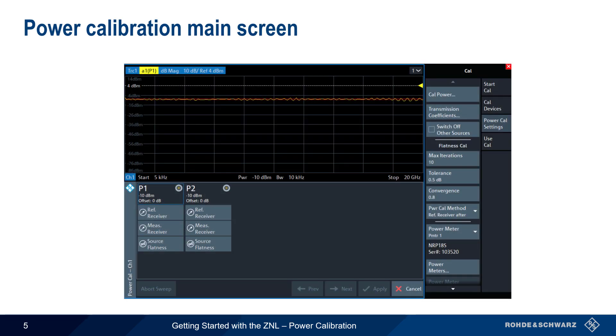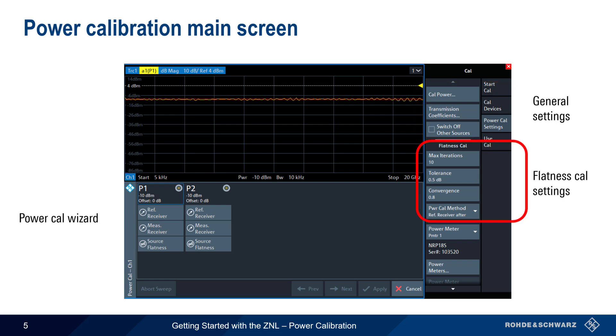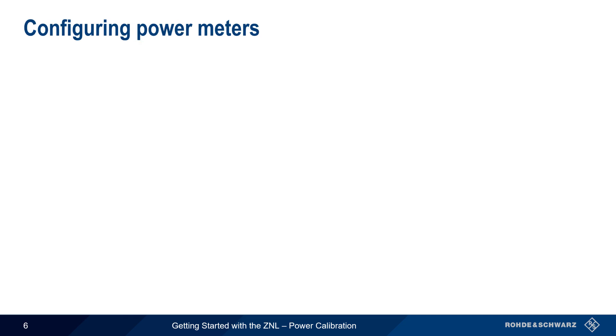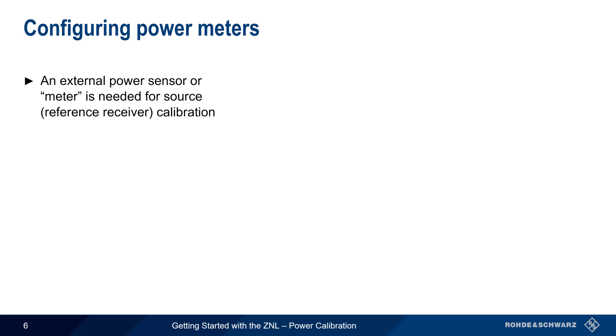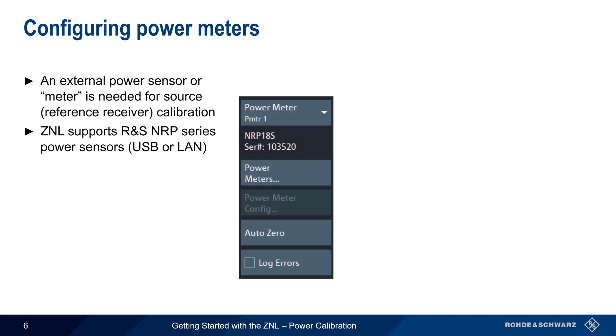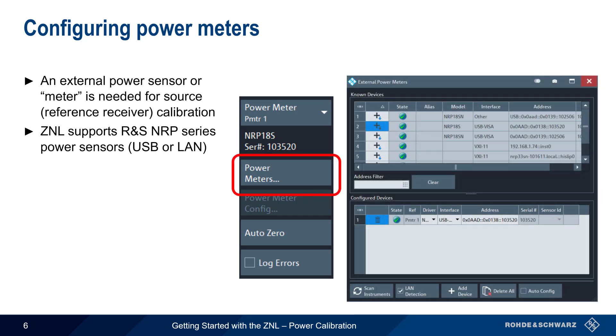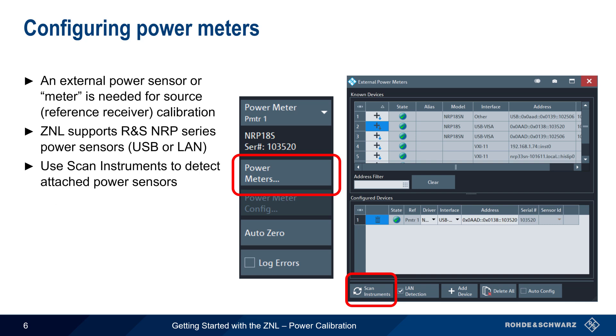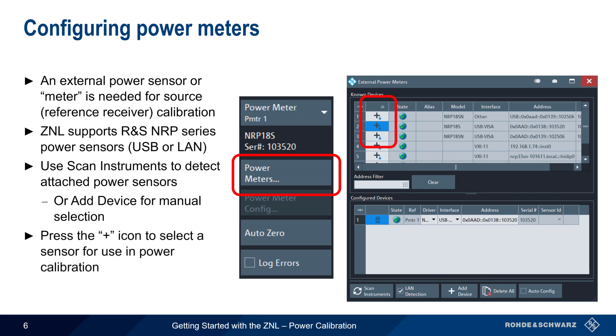The Power Calibration GUI has four main areas: the Power Calibration Wizard, General Settings, Flatness Calibration Settings, and Power Meter Settings. Since source or reference receiver calibration requires the use of a power meter, let's start with Power Meter Settings. An external power meter is needed when performing source or reference receiver calibration. The ZNL supports most Rohde & Schwarz NRP Series power sensors, including both USB and LAN models. These sensors are configured under the Power Meter tab. Clicking on this tab brings up a list of connected power sensors. Scan Instruments can be used to automatically detect attached power sensors, or Add Device can be used to configure them manually. Press the plus icon to the left of a power sensor to select it for use in power calibration.